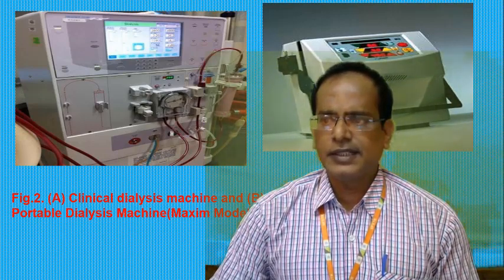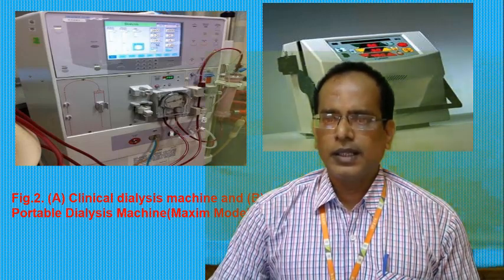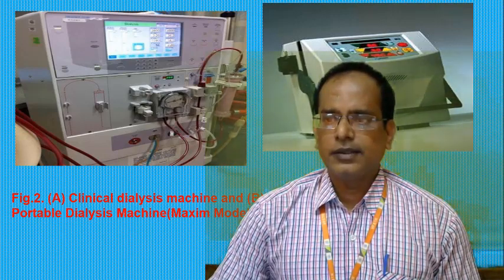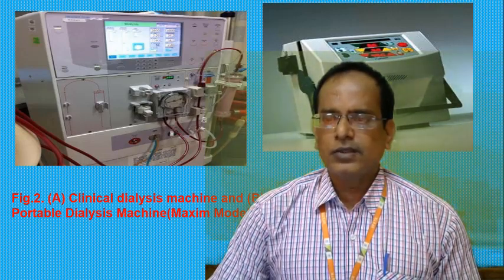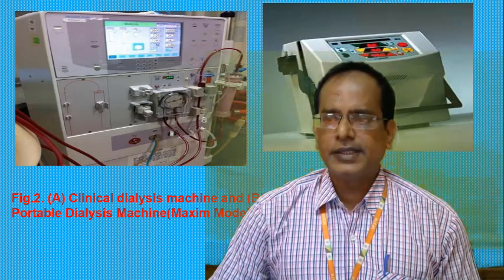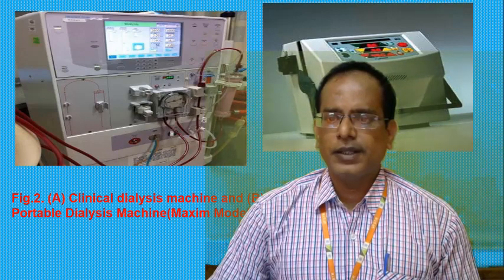The principle of hemodialysis is the same as dialysis in our kidney — it involves diffusion of solutes across a semi-permeable membrane. Hemodialysis utilizes a counter-current flow method where the dialysate flows in the opposite direction to the blood flow in the extracorporeal circuit. This counter-current flow maintains the concentration gradient across the membrane at a maximum, which increases the efficiency of dialysis.